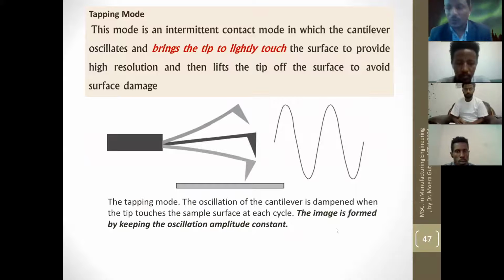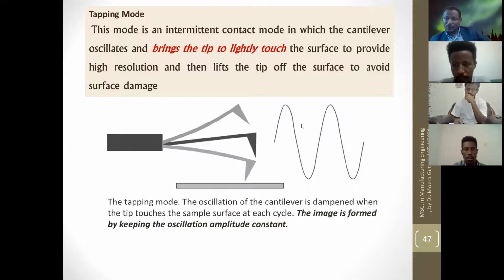The other one is intermittent. When the cantilever beam is in intermittent mode, it touches the surface and, at a very small frequency, leaves the surface of the sample. What happens here? As you see from this figure, at the current position of the probe, the cantilever beam is this one, the black one. It can be here, it can be there. So the rule is you have to control the constant amplitude changes. Oscillation amplitude should be maintained constant here.